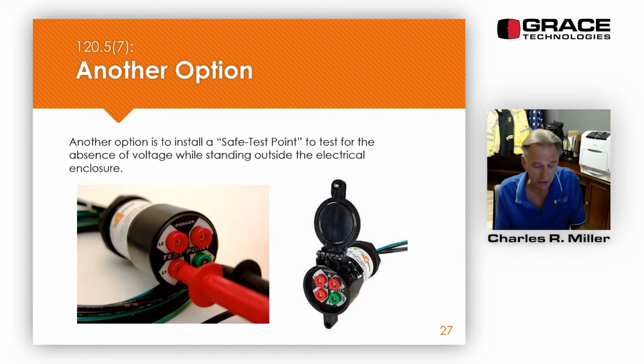You are testing your meter to make sure it's operating properly through verification on any known voltage source. Then from outside the cabinet, you are testing phase to phase and phase to ground. Then you're testing your meter on any known voltage source. Of course, regardless of the device, it has to be installed in accordance with the instructions. This is just more of a remote testing. If it's installed properly, you're doing the testing properly from the outside. If it's installed on the line side, you know the cabinet is electrically safe after doing this.